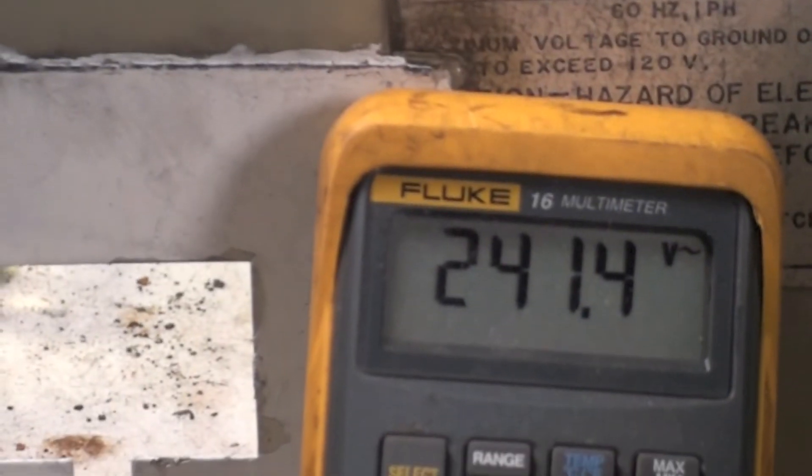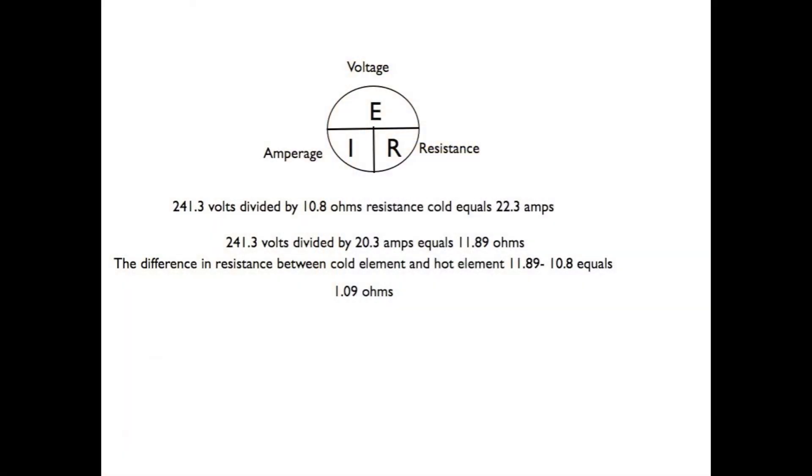So we're going to do some calculations here to determine what the actual resistance is. Okay, we can use EIR to calculate this, and we had 241.3 volts. We divide that by the 10.8 ohms resistance that we read cold, and that equals potentially 22.3 amps if the element was cold.